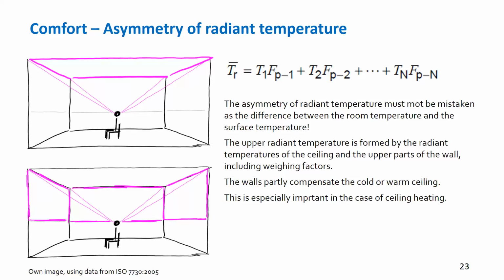And having said this, we know that a heated ceiling, in a usual room of a usual size, can be heated up to 6 degrees more than room temperature without any comfort problems. So if we have a room of 22, we can easily allow ourselves a ceiling with 28. And we do this and nobody complains. And then we have a ceiling heat flux of 40 watt per square meter. And from the cooling side, there's no comfort problem, because we are so robust against cooling from above.